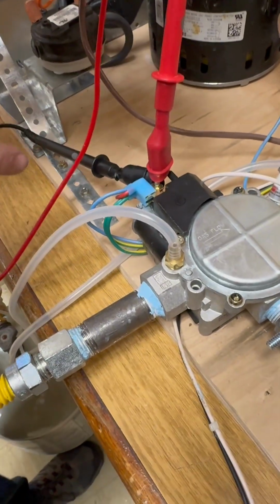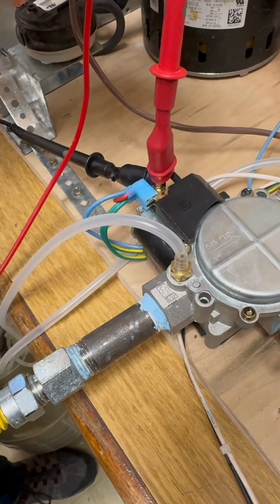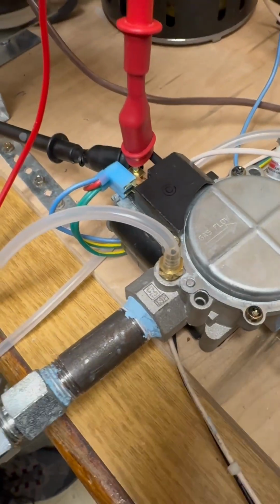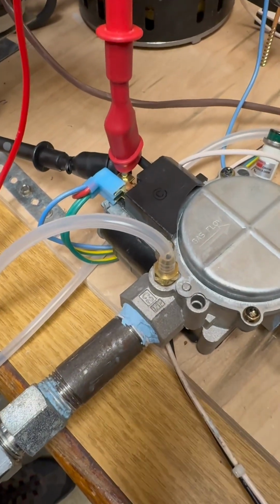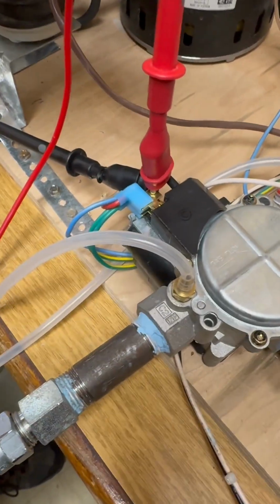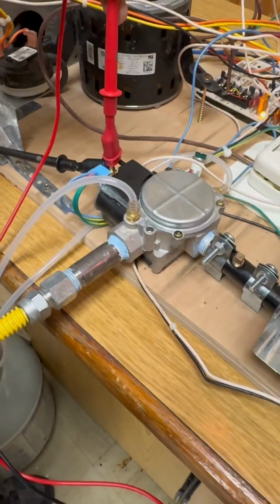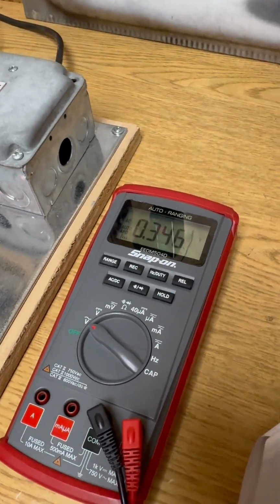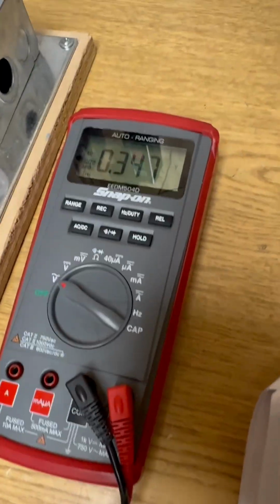We're using a spade connector to be able to get our power in and be able to get a meter probe on it. The spade connectors are a must when you're trying to work, because you can't get the probe in there without the spade, it's really hard. So always use a spade just to get a good reading on your meter.